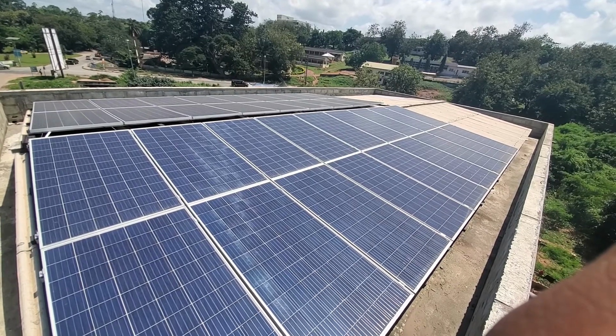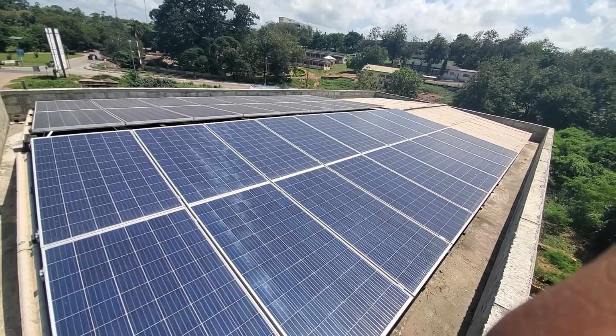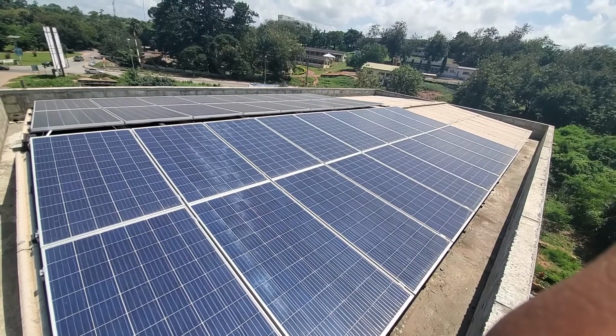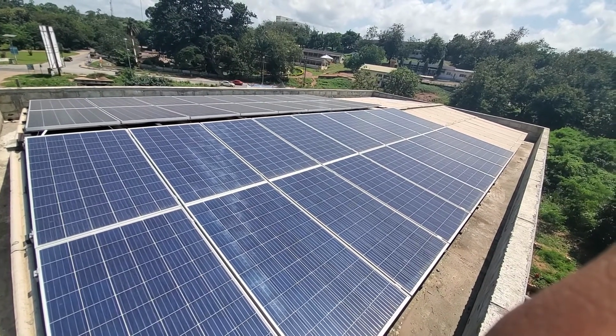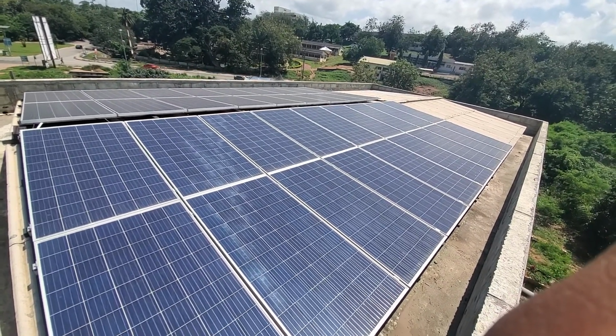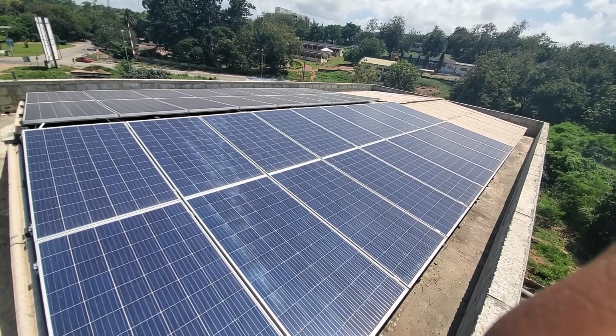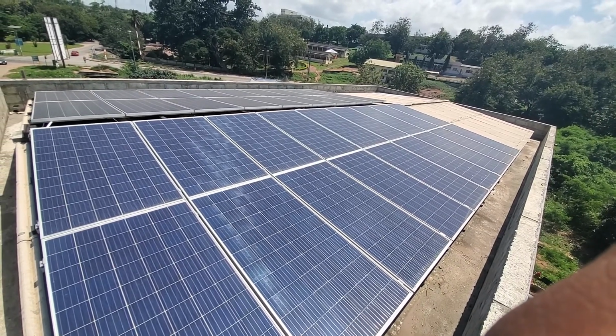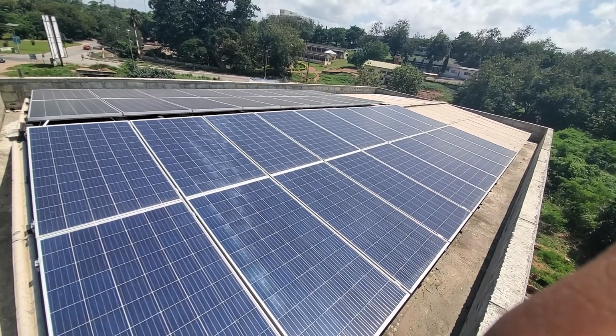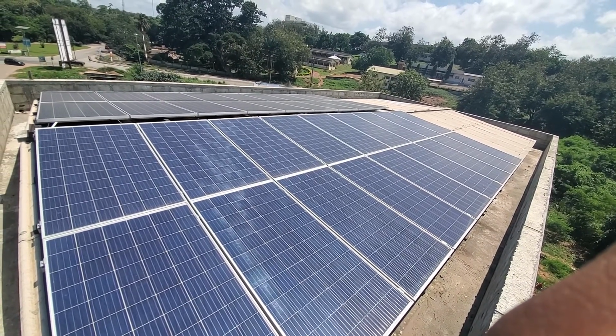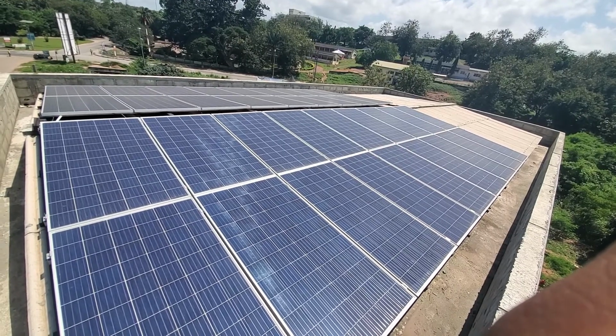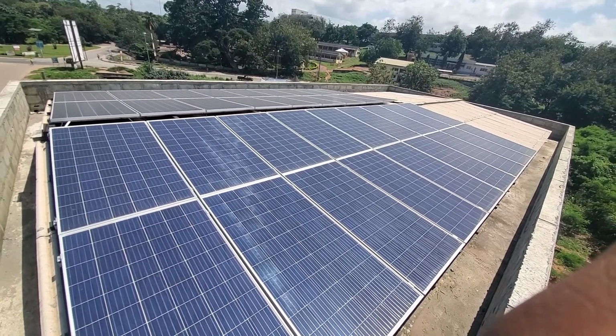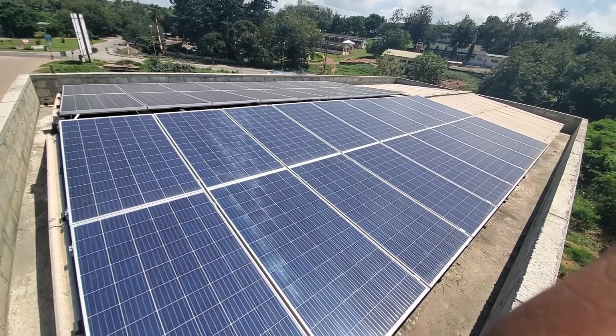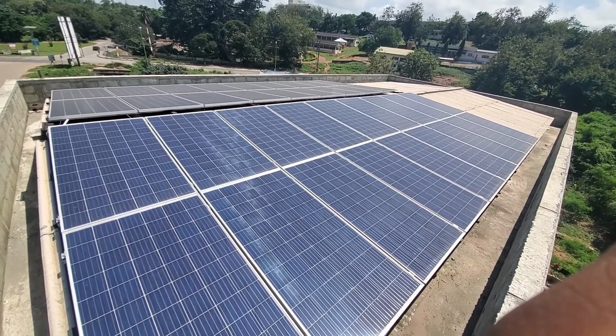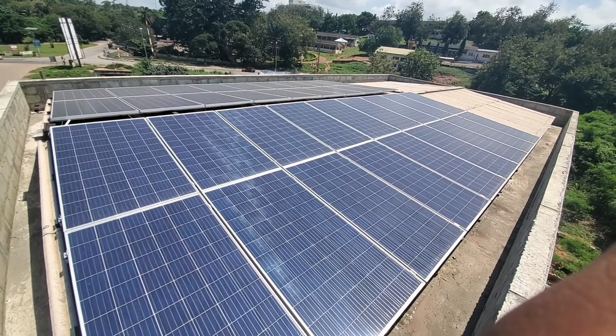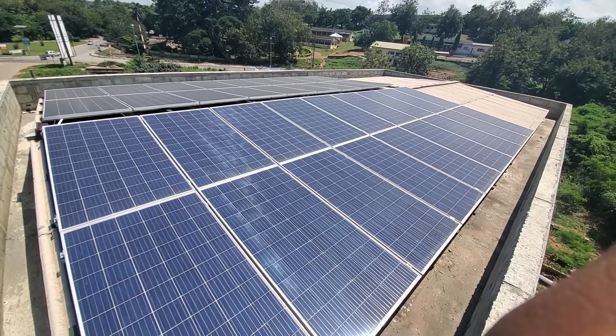So 36 at 325 watts means that this installation has a total capacity of 11.7 kilowatts. For peak sun hours of 5.5 in Ghana, you can harness energy of 11.7 times 5.5, which will give you about 64.35 kilowatt hours in a day. All right. This is the little bit I can give you about the solar panels. Let me take you to the inverter and then we see what is there.